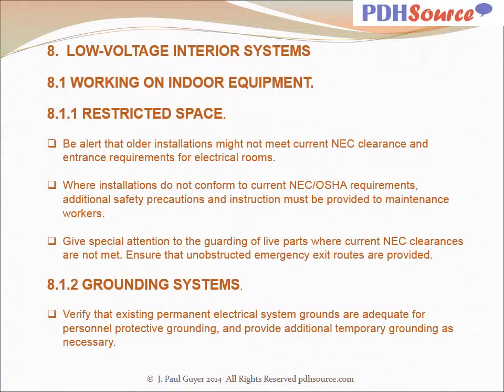Now we will proceed to discussing low voltage interior systems. Working on indoor equipment in restricted spaces, be alert that older installations might not meet current NEC clearance and entrance requirements for electrical rooms. Where installations do not conform to current NEC OSHA requirements, additional safety precautions and instruction must be provided to maintenance workers. Give special attention to the guarding of live parts where current NEC clearances are not met. Ensure that unobstructed emergency exit routes are provided. With regard to the grounding systems, verify that existing permanent electrical system grounds are adequate for personnel protective grounding and provide additional temporary grounding as necessary.